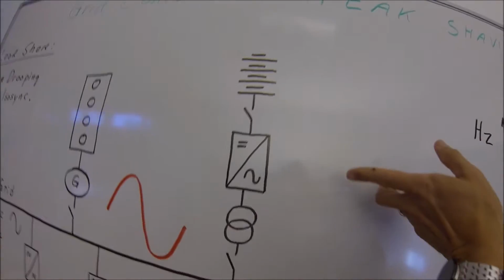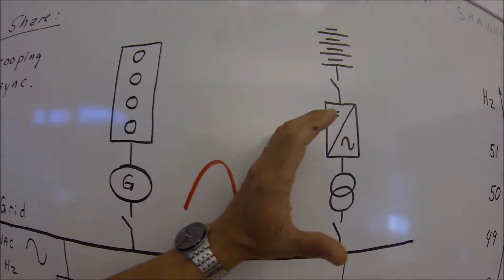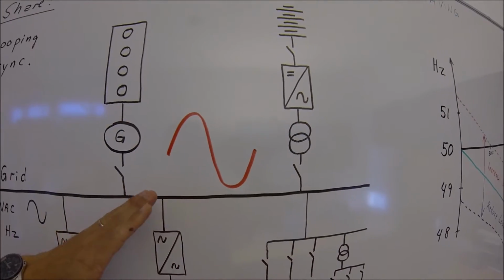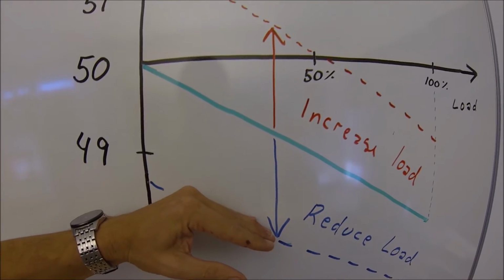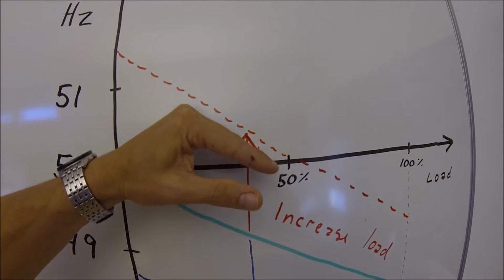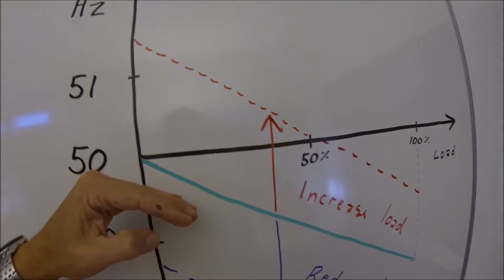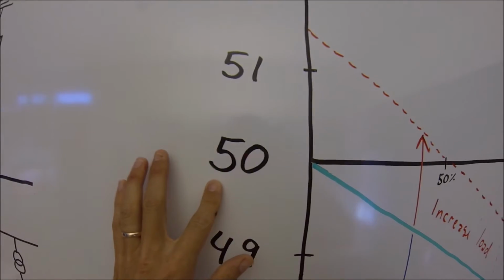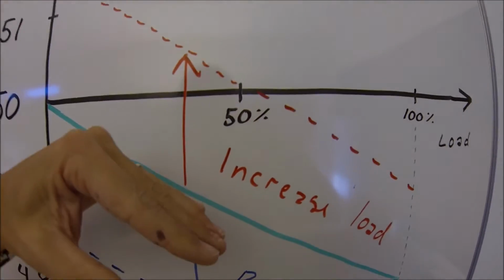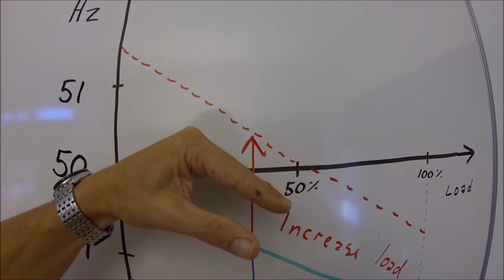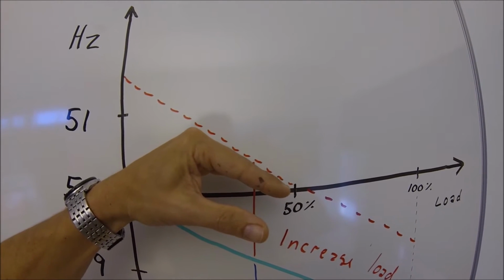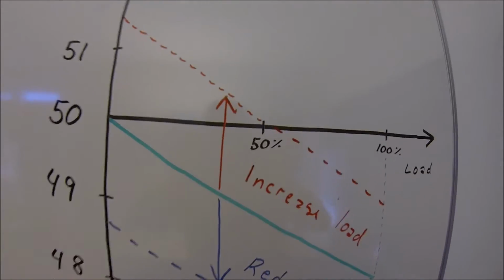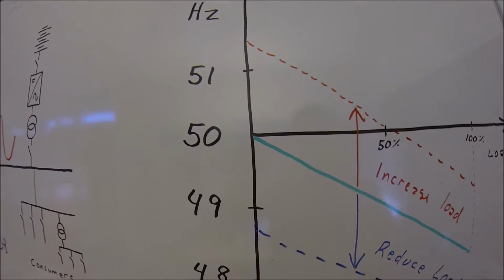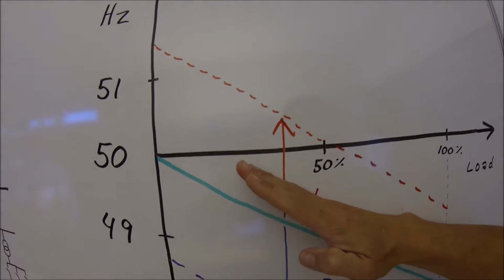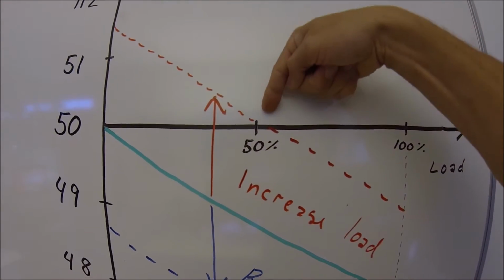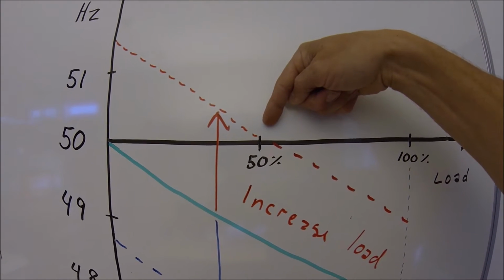And when the power management tells me to start pushing on the grid to take active load, then I lift my curve, and I can lift it quite high. I can go up to maybe here. And then even at 50 hertz, I could take 50% load. So with the reference lifted, when there is a command from the power management to take load in isosynchronous mode, I basically just adapt to whatever frequency is on the ship grid and adjust up to whatever is needed to hit the reference given by the power management.